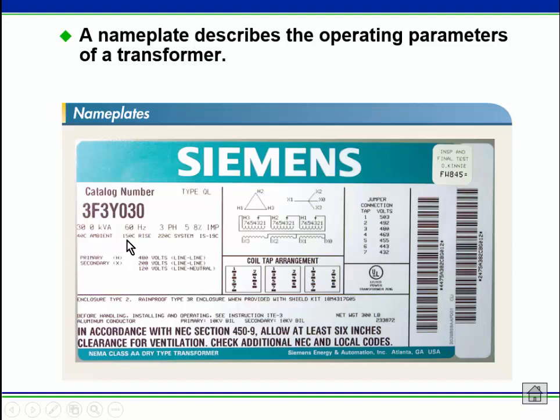Let's see here. This is assumed 40 degrees ambient. That's when you can put the 30 kVA on it. And here's the BIL. BIL has to do with how much voltage it can stand for just a little bit. Basic impulse insulation level. We'll look at that closer when we do surge arresters. And I think that's enough for that.